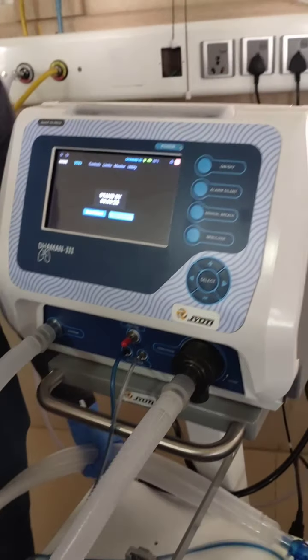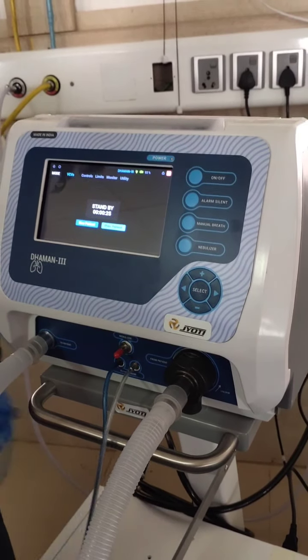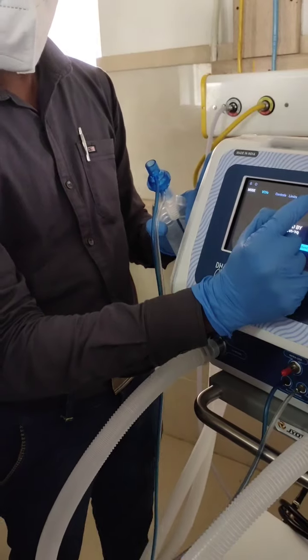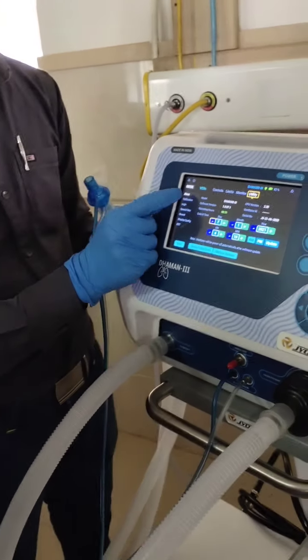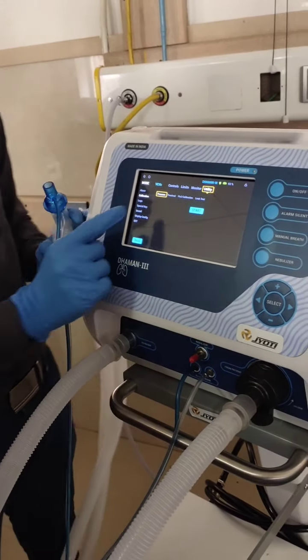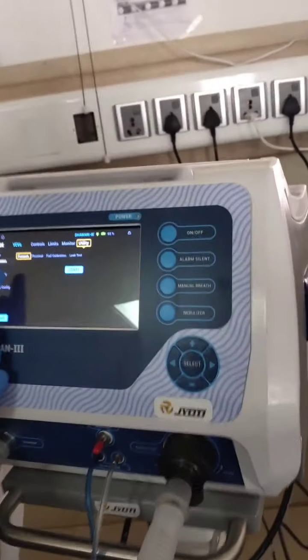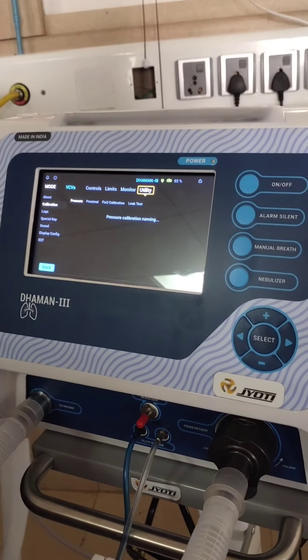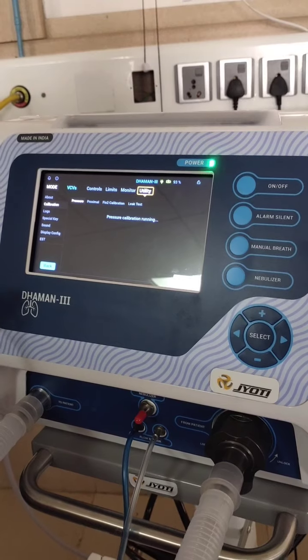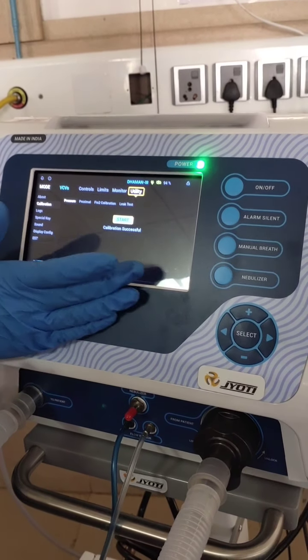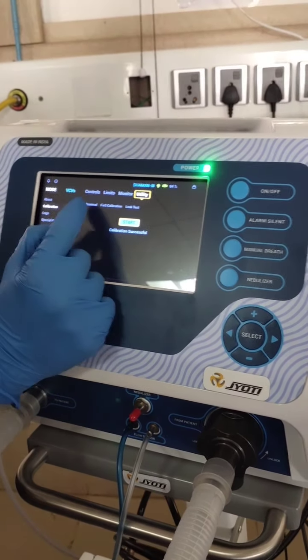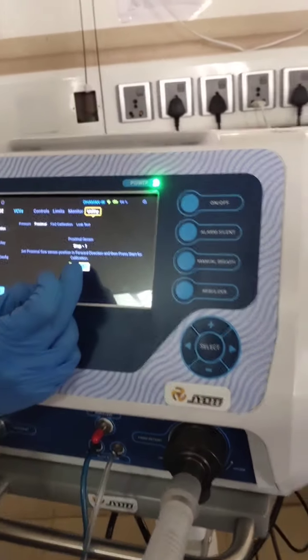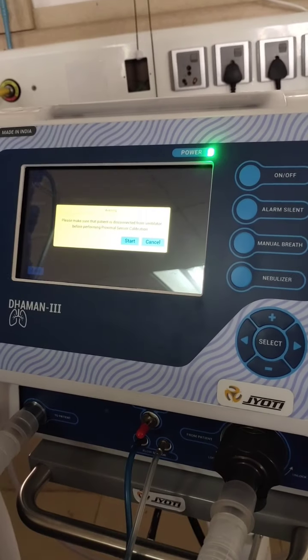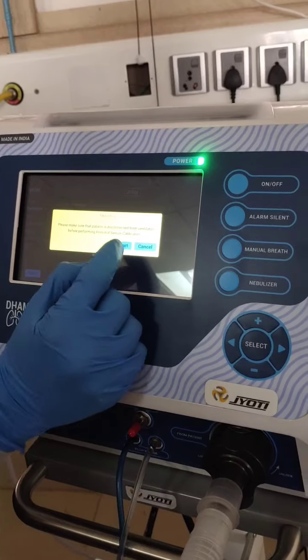Okay. First of all, we connect this proximal sensor while the window comes. Before the patient connection you have to do some calibration. So go to the utility and then go to the calibration. First we have pressure. Then start. It takes 30 seconds. Once the calibration is successful, go to the proximal sensor. Then start for the forward direction. So this is the forward direction. Then you have to start.